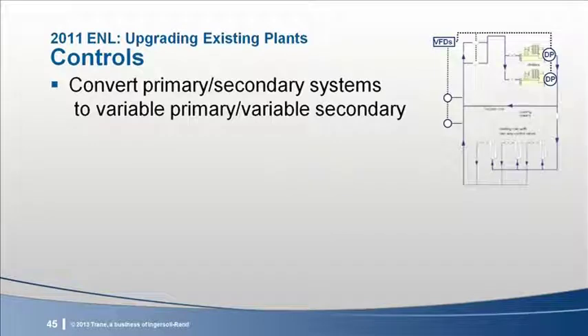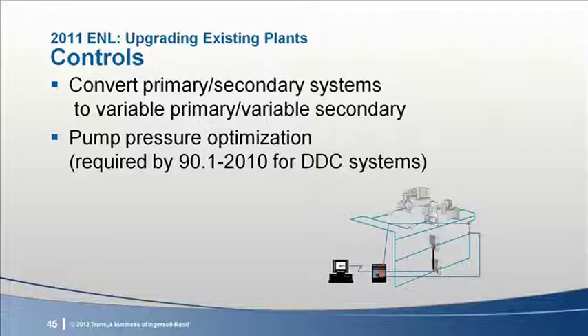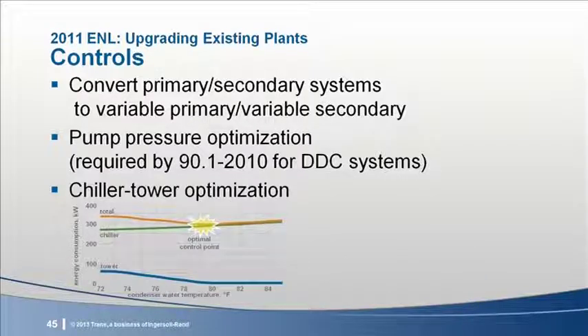From a retrofit and controls perspective, rather than converting from a primary secondary to full variable primary, a more cost-effective solution may be to convert to variable primary, variable secondary. If air handling valves have direct digital control, use that valve position to optimize pump pressure at all operating conditions. And use a VFD on the cooling tower fan to optimize the sum of the chiller plus tower energy consumption. We'll see quite a bit more about this today.